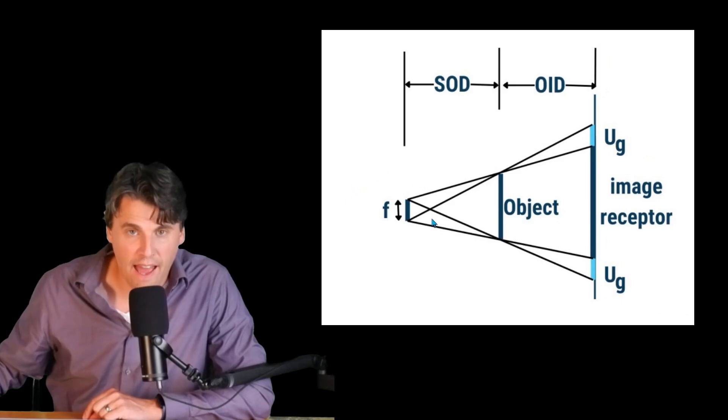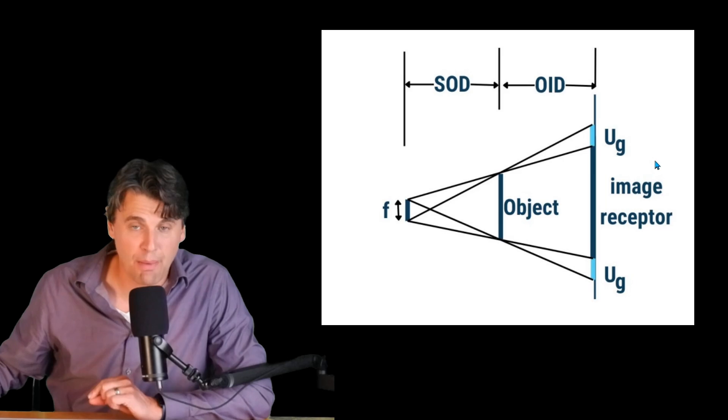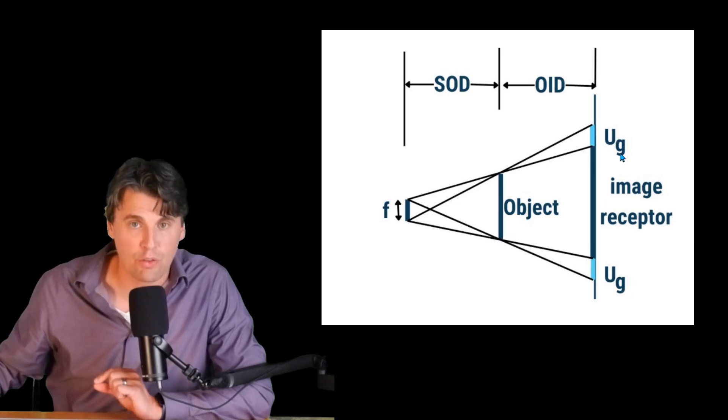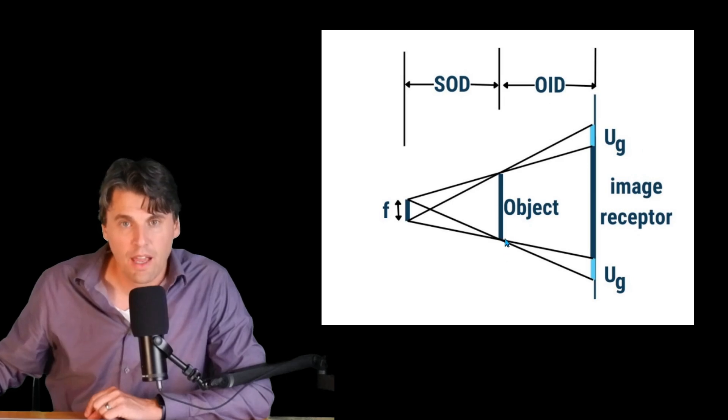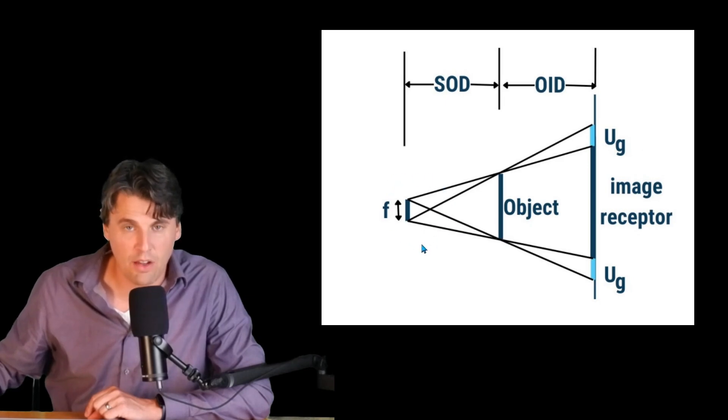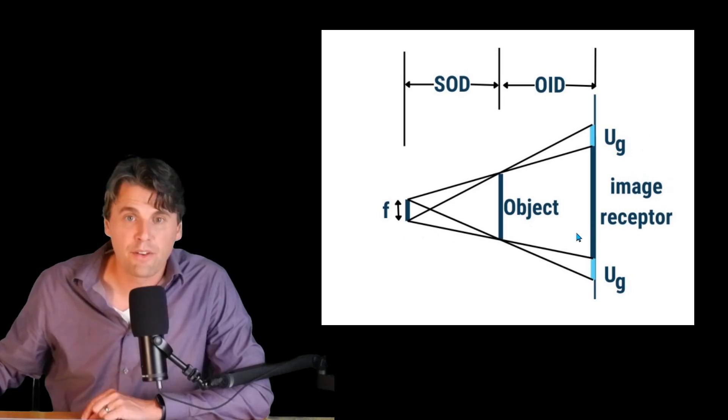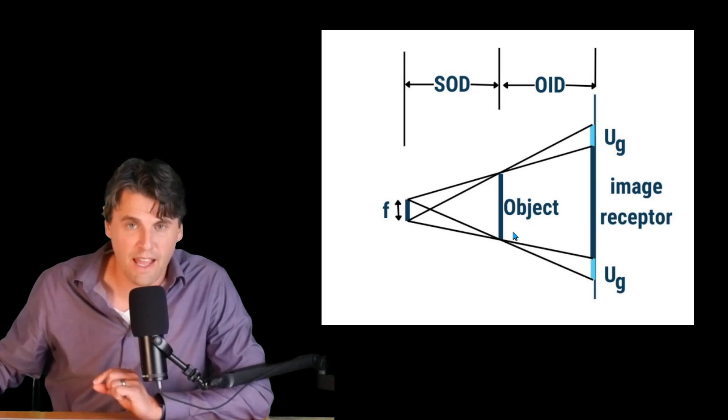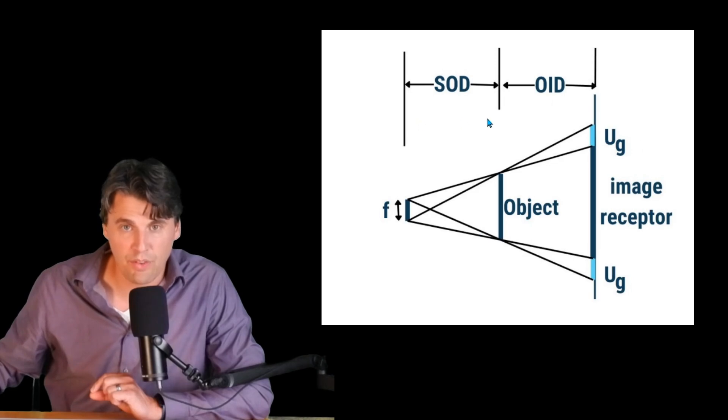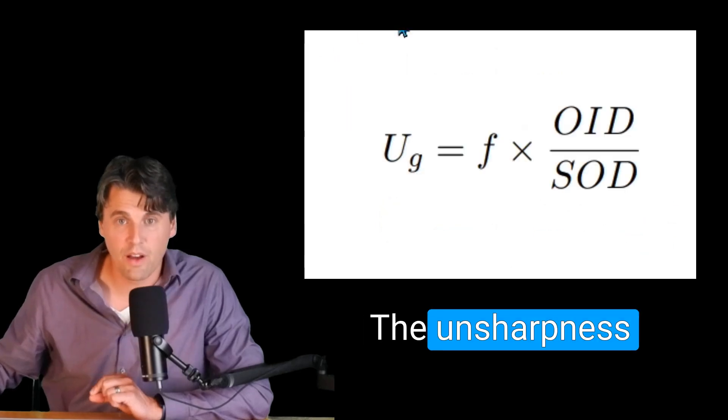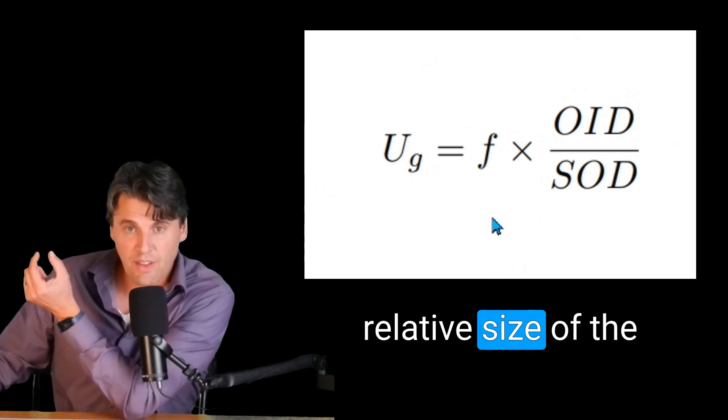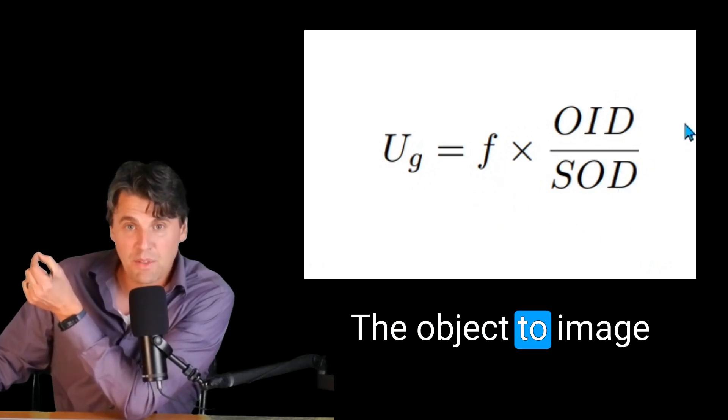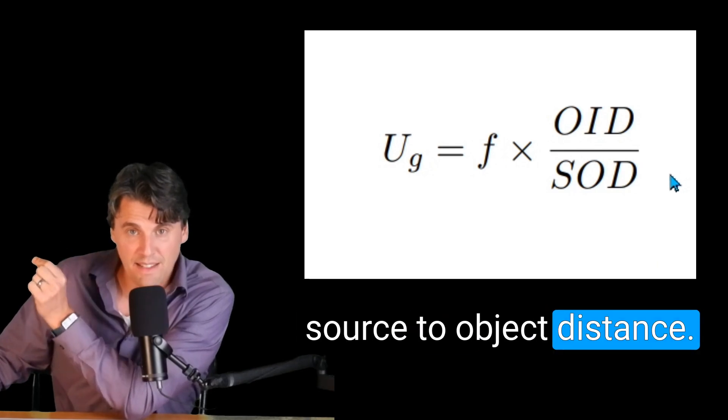We can see what that looks like here. If you look at F is the size of the focal spot, and then U is our geometric unsharpness. That distance right there is the distance over which there's blurring due to the focal spot. Then you have your object here in the middle. And so you can see, like we talked about, the focal spot as it gets larger, that is directly going to lead to this unsharpness getting larger. There's also a term that is essentially having to do with the geometric magnification here. Right here we have the source to object distance, and we have the object to image distance. The unsharpness is actually just the relative size of the focal spot times the object to image distance divided by the source to object distance.